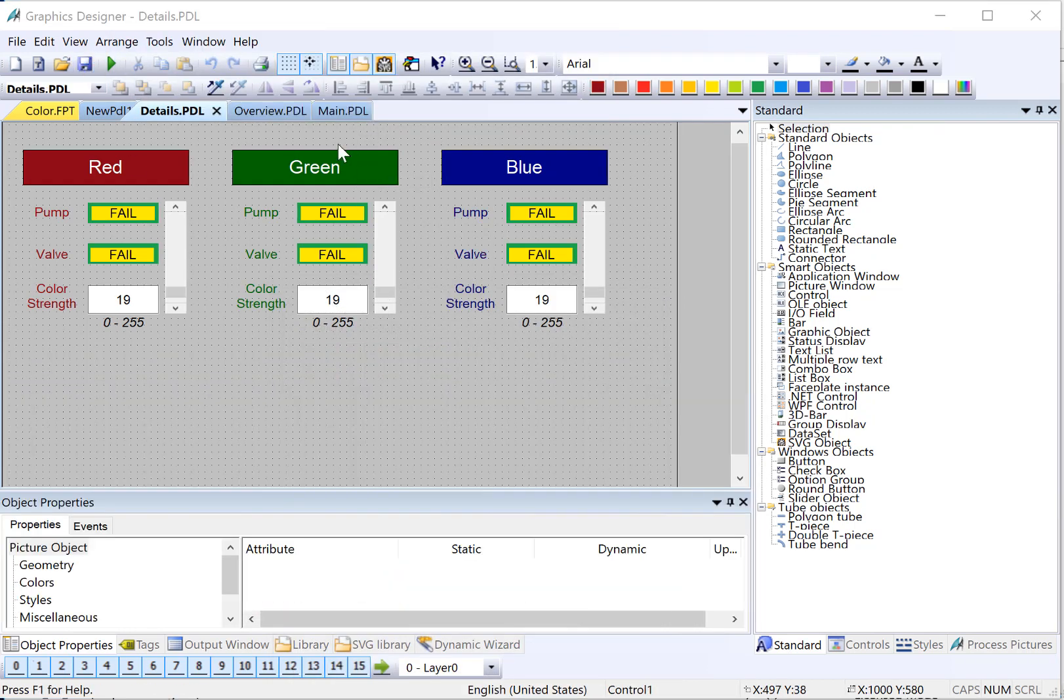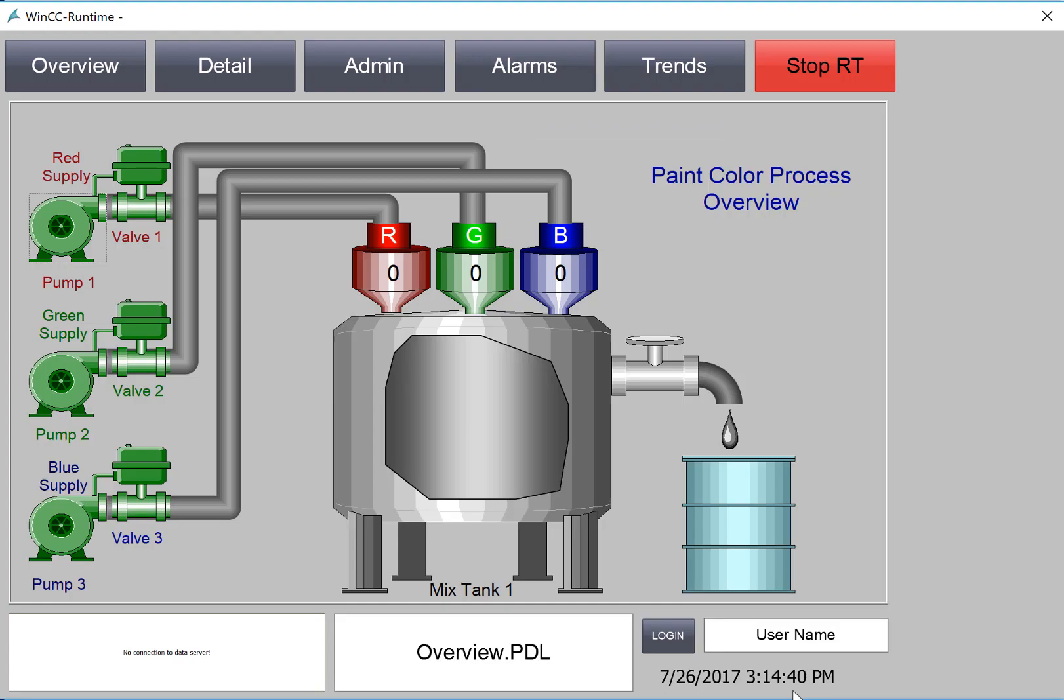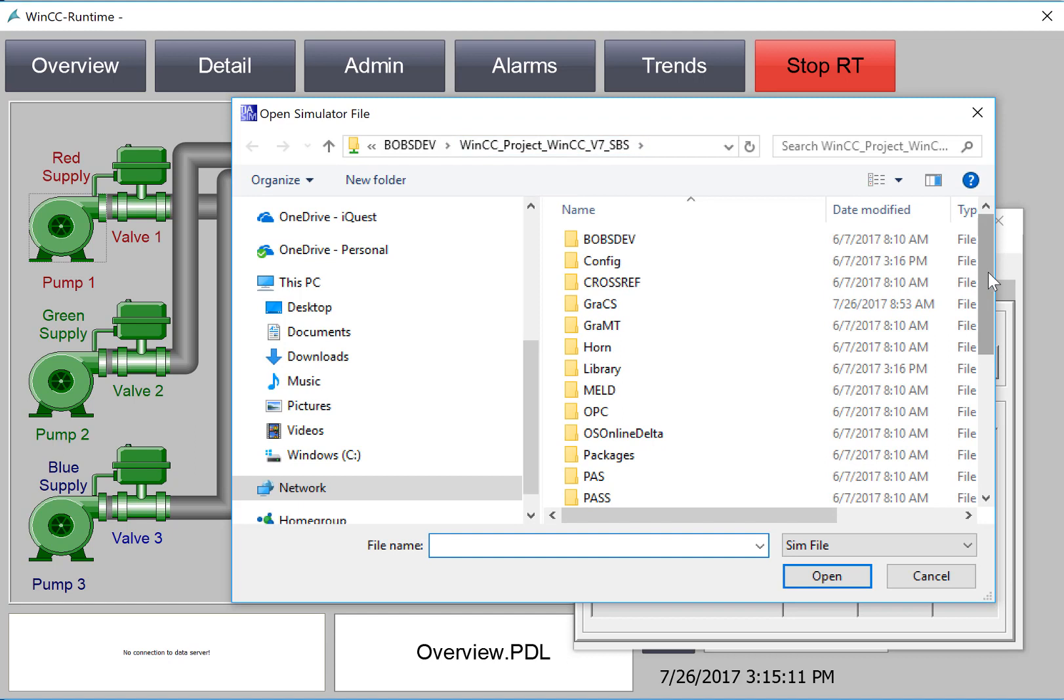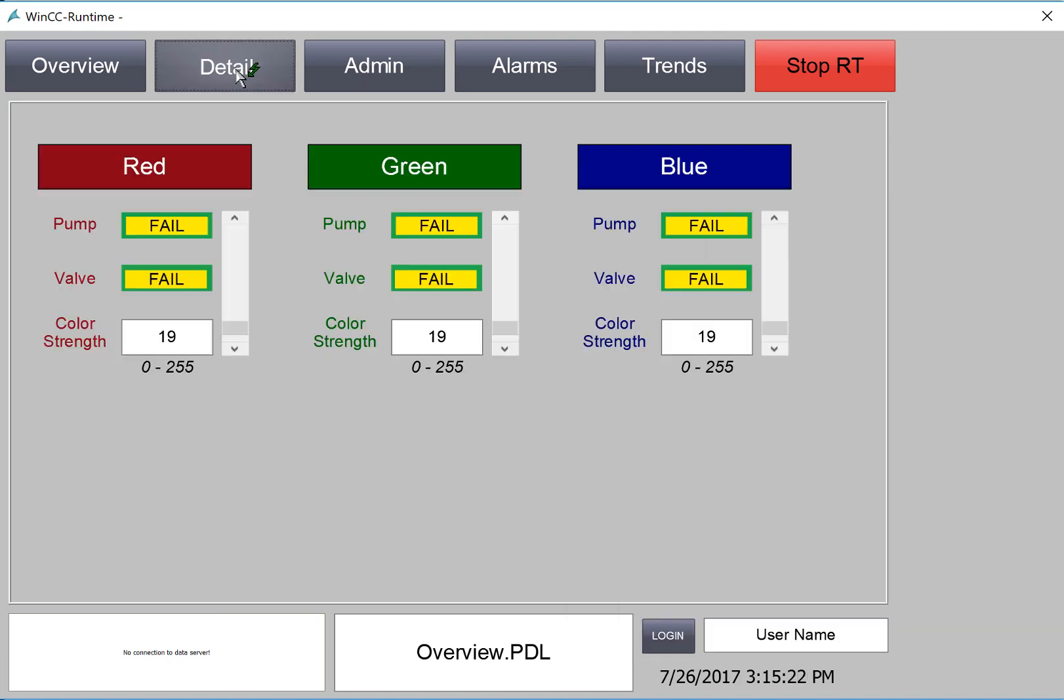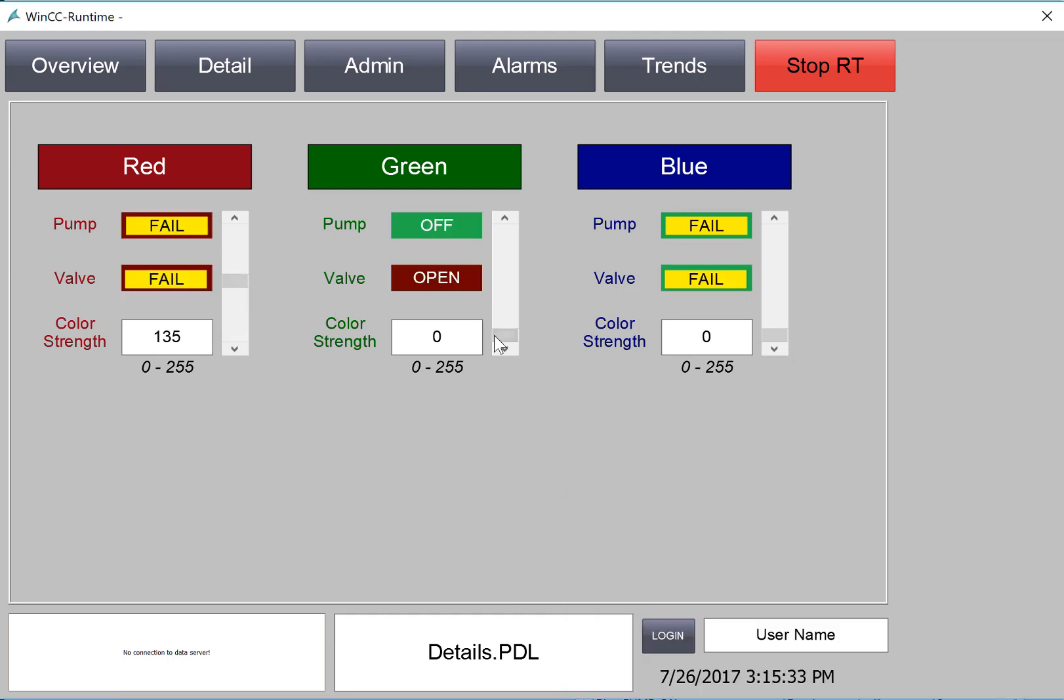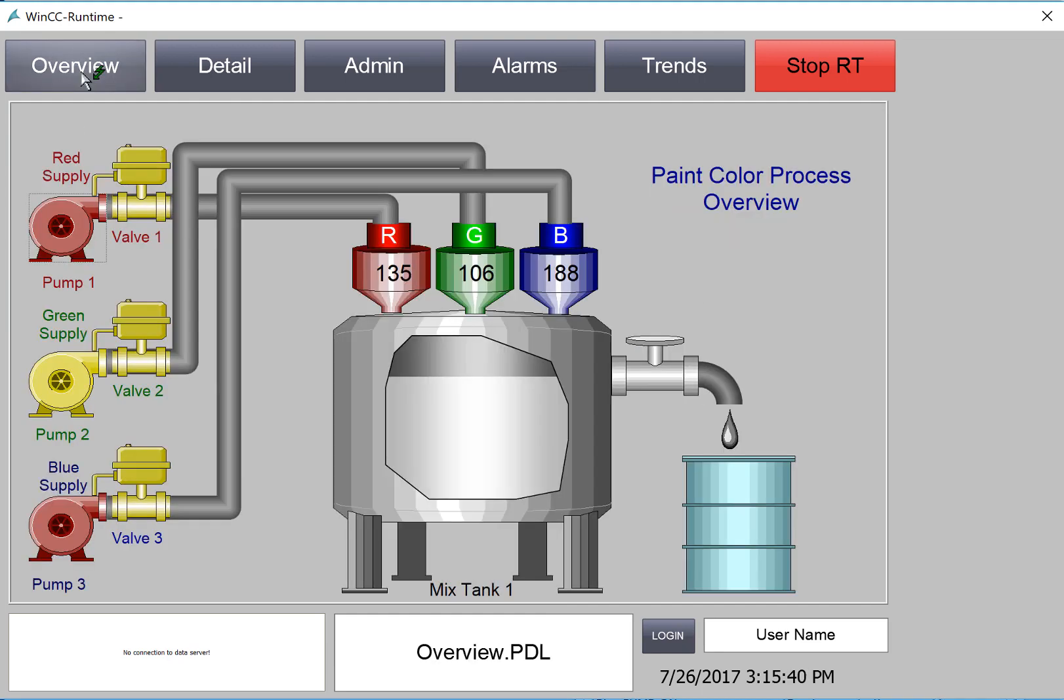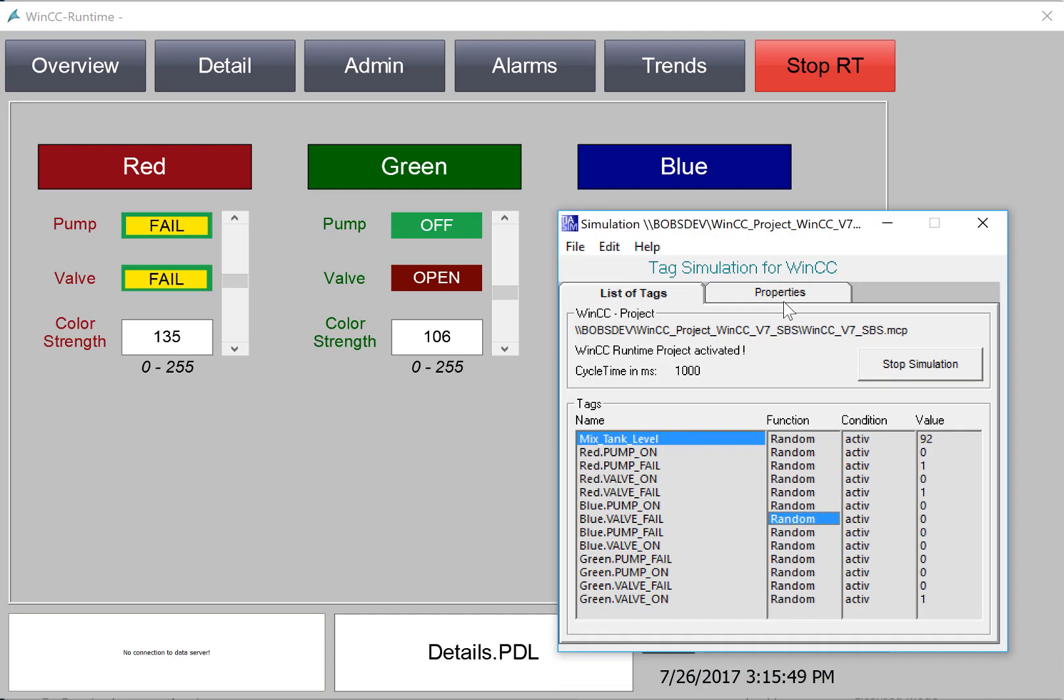Now all we need to do is test this in runtime. I'm going to open my main screen and just press runtime. And I'll also bring up my tag simulator. In the tag simulator, we'll need to open the sim file that we saved. So I'll do open, and it will automatically go to whatever project WinCC has open, and just go to the bottom and look for the sim file. And then just start simulation. And then on our detail screen, you should see the different controls working based on what the simulator is doing. And we can control our color strength with our sliders. And then if we go back to our overview page, you can see that those tags are also represented there. So it looks like our detail screen is working.